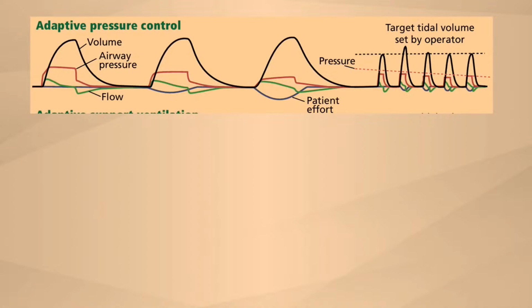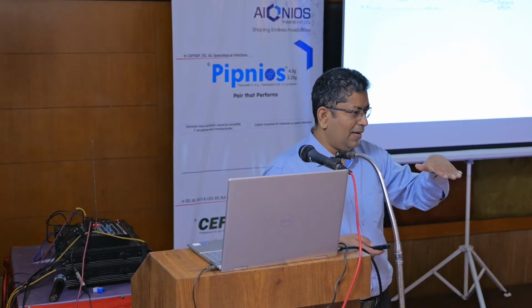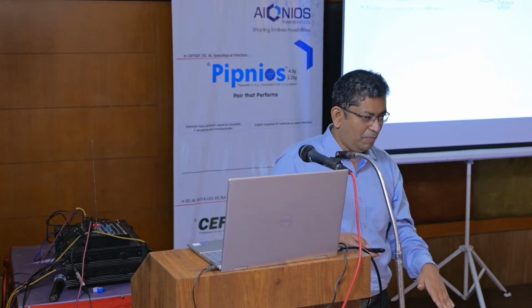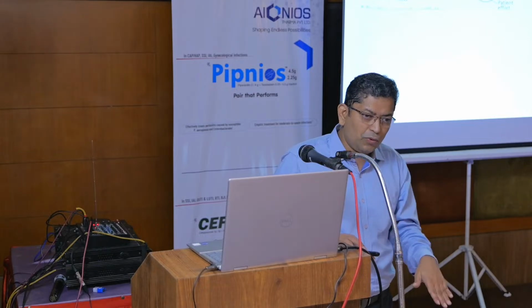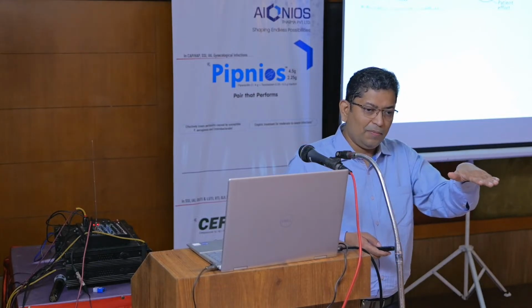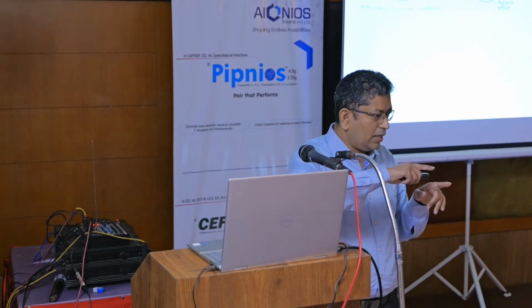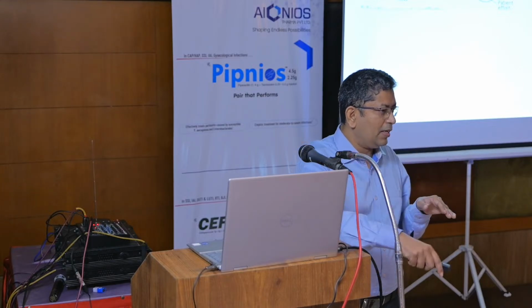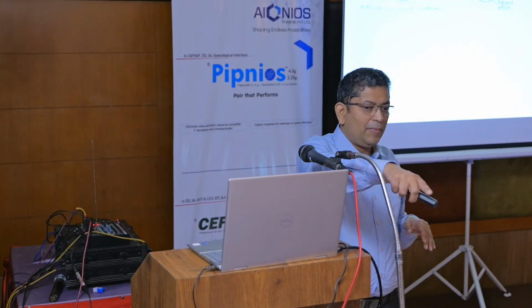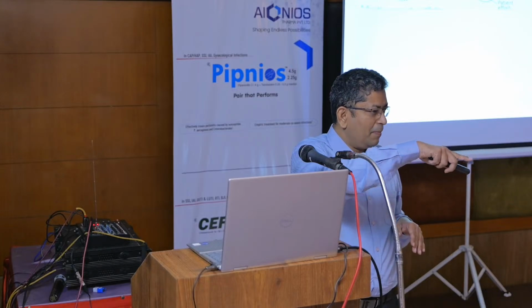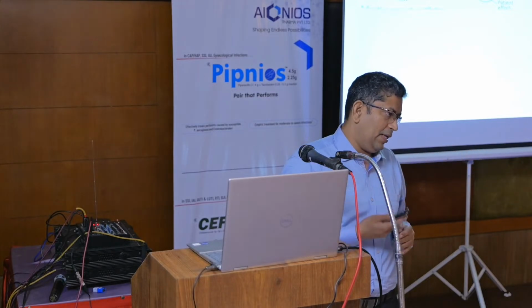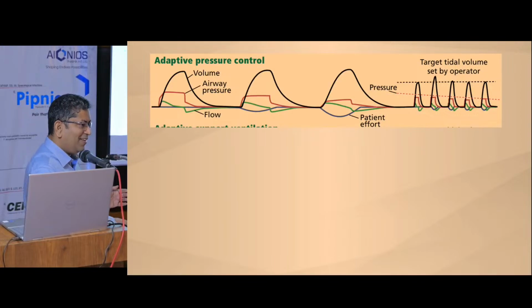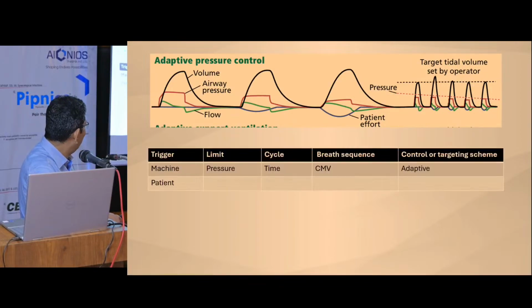All right. So usually what happens is, it will give one breath and see. If the pressure is more, next breath it will reduce the pressure support. All right. If it's too low, next breath it will increase the pressure support. And so, breath by breath, the pressure support can keep changing till the machine finds out what pressure the patient needs. All right, clear? Nice mode. Yeah, very useful. Yeah. All right.